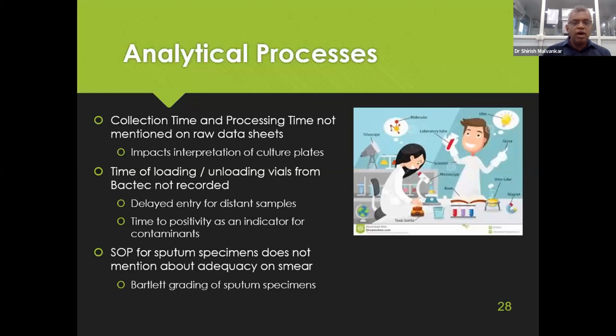Time of loading and unloading vials from the BacTec is not recorded. Now, this is again important. If you know the time of sample collection, and if there is a delayed entry for distant samples, where the sample has arrived from a laboratory or a center which is quite a distance away, then you have to be aware that sometimes the scanning log of the BacTec instrument may not pick up a delayed entry vial, and it needs to be adequately looked at.